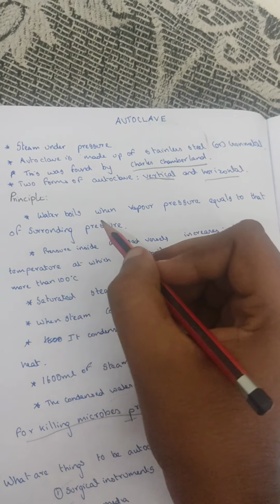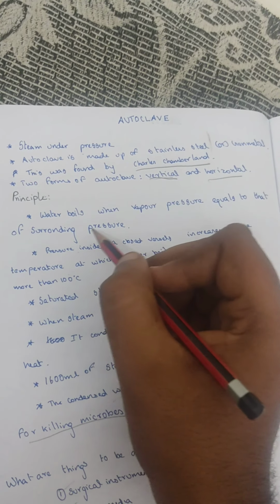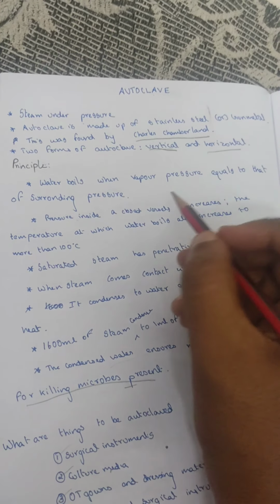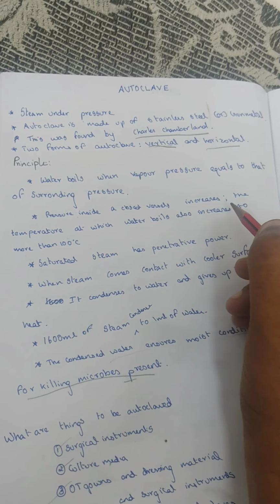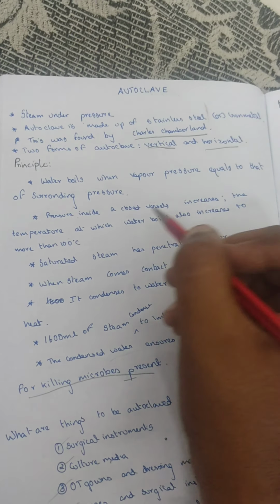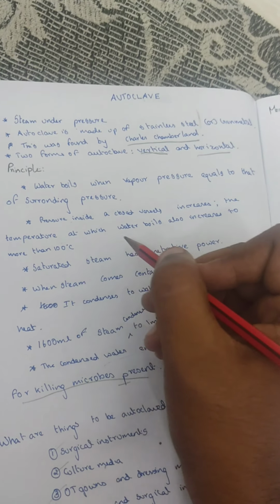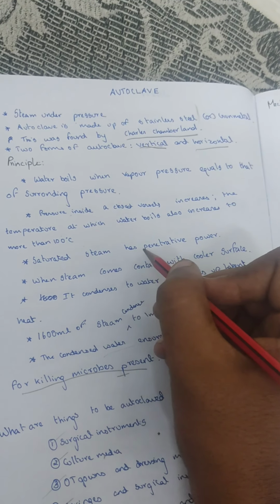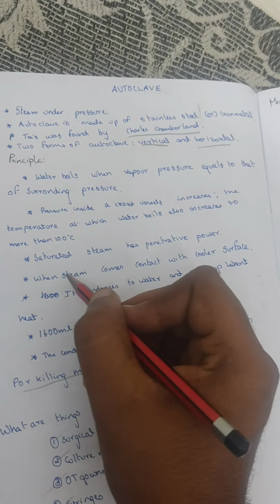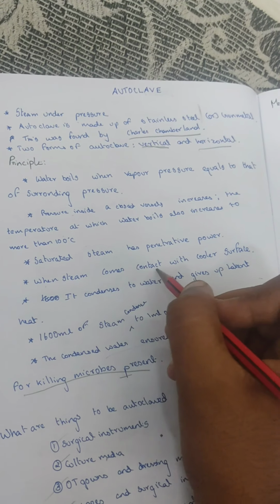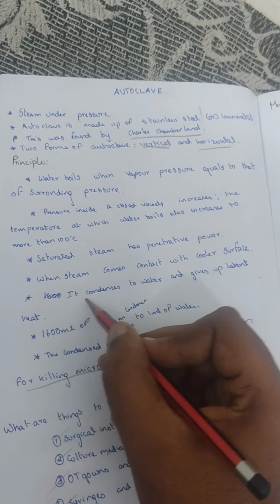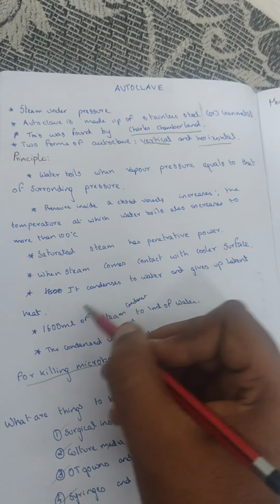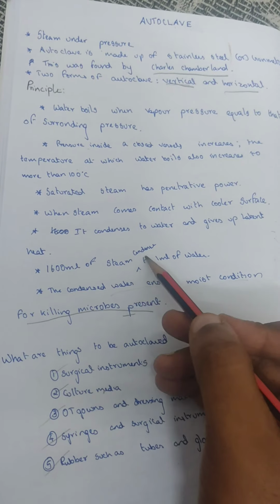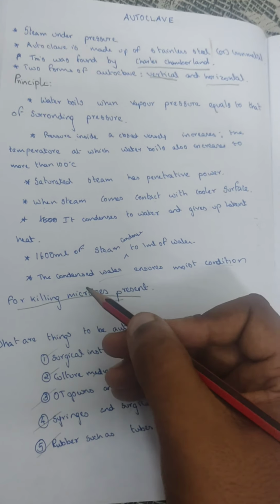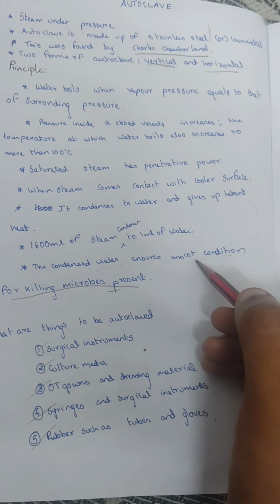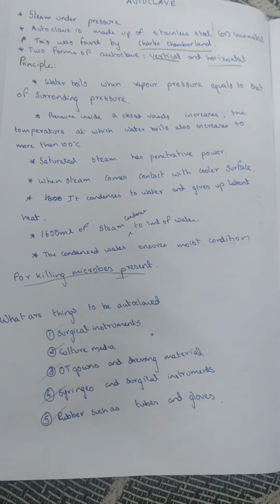Principle: water boils when the vapor pressure equals the surrounding pressure. The pressure inside the closed vessel increases, and the temperature at which the water boils also increases to more than 100 degrees Celsius. The saturated steam has penetrative power. When the steam comes in contact with a cooler surface, it condenses to water and gives off latent heat. 1600 ml of steam condenses to 1 ml of water. The condensed water ensures a moist condition for killing the microbes present.